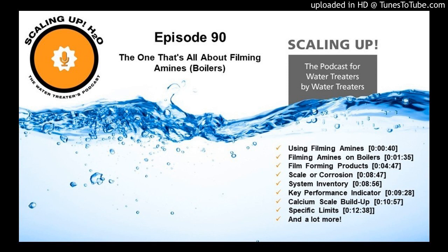If it is an option to let it circulate and then drain it out, my preference is always just to get the crud out, truly. The nice thing about boilers and cooling towers is that there's a bleed, there's a flushing system built into how they function. And in the beginning, when you first bring these things online and it goes through this cleaning process, it's got to get out of there. So blow it down, blow it down, blow it down. Blow down your mud drum extra if it's possible.